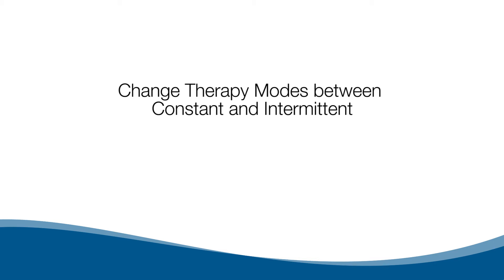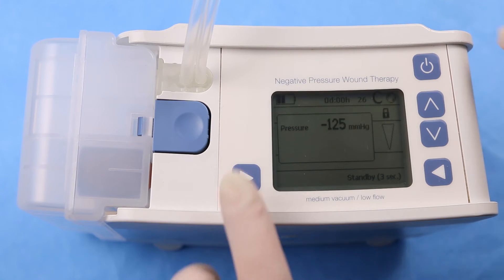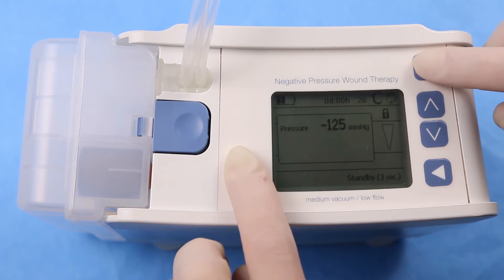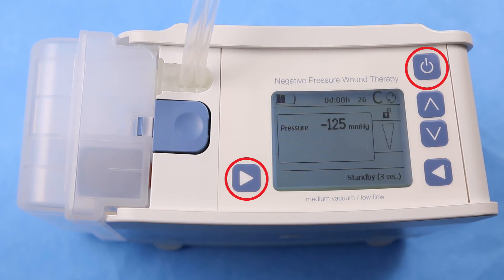To change therapy modes between constant and intermittent, the pump must be placed in administrative mode. To enter the administrative mode, press and hold the bottom left button and press the top right button.